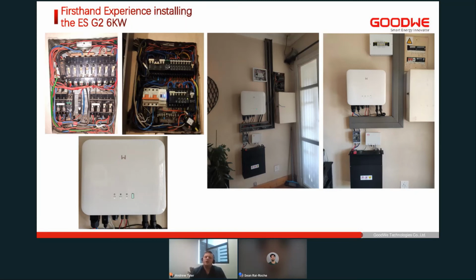And then just to show you the ESG2, one of our beta installations, some examples. It's always nice to be able to refer back to this and see exactly how the system looks. This is a 6 kilowatt ESG2, which has a BYD Flex Lite 5.4 kilowatt hour, if I'm not mistaken, connected to it. You'll see on the top left, there are 2 DB board pictures. The left is the before and the right is the after. This was a really, really old house with a very old DB board. You'll see the switches, the breakers rather, are quite large, and for this installation, the entire DB board was replaced with modern breakers, so it takes up a lot less space. And then you'll see in the middle of the second picture that the GoodWe energy meter is installed there.